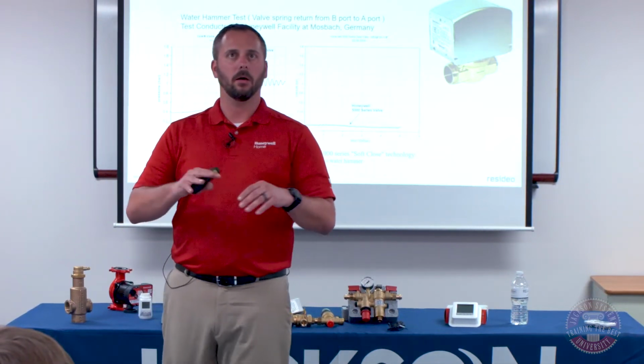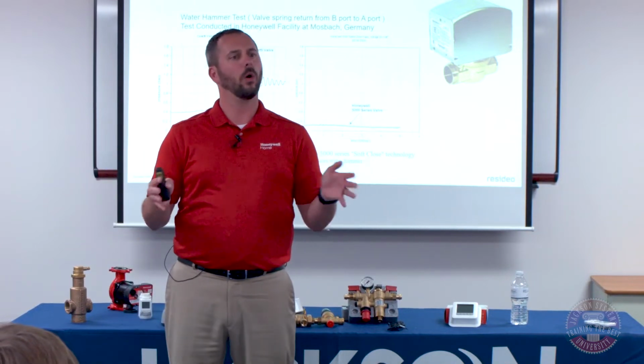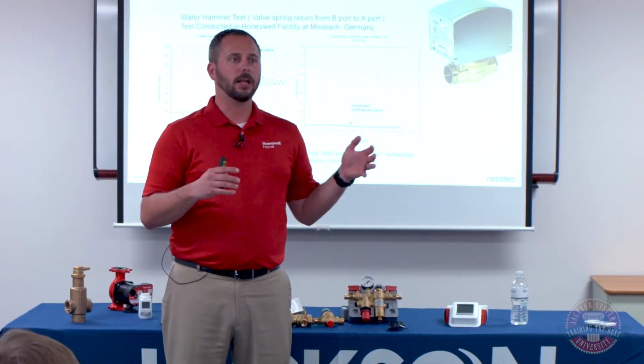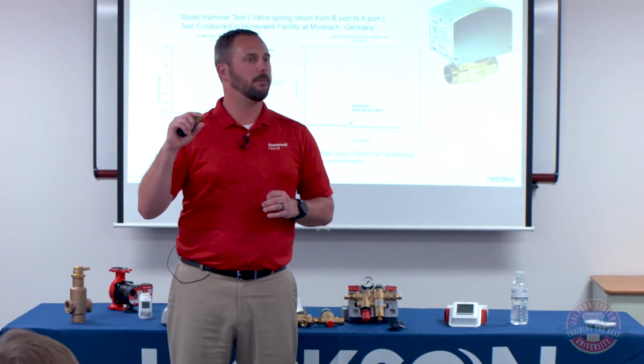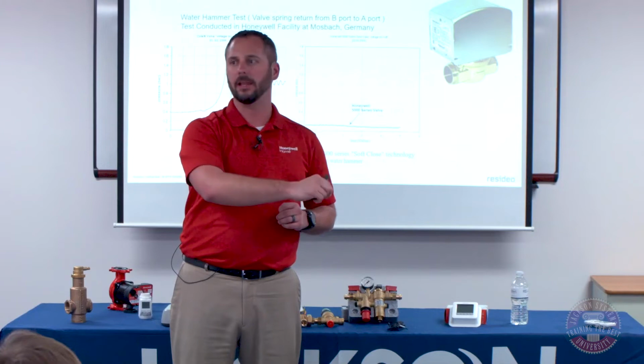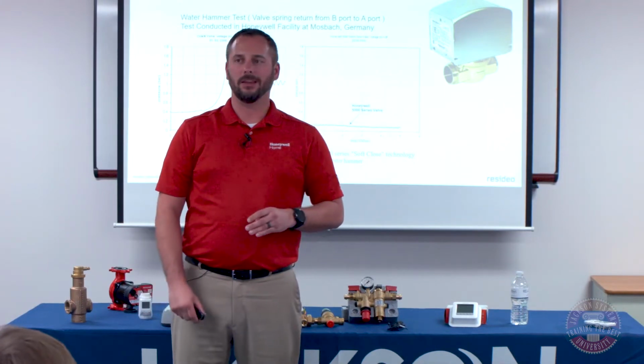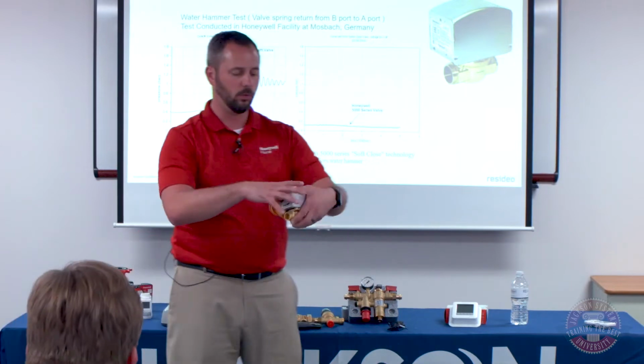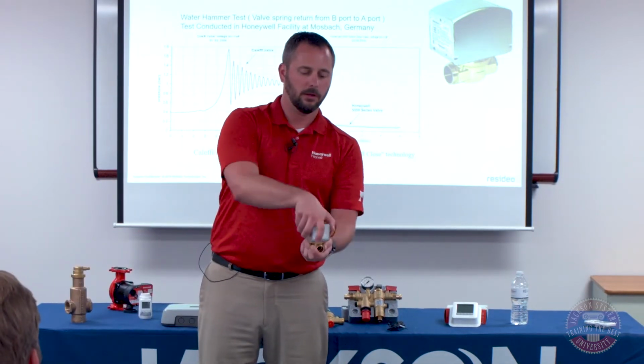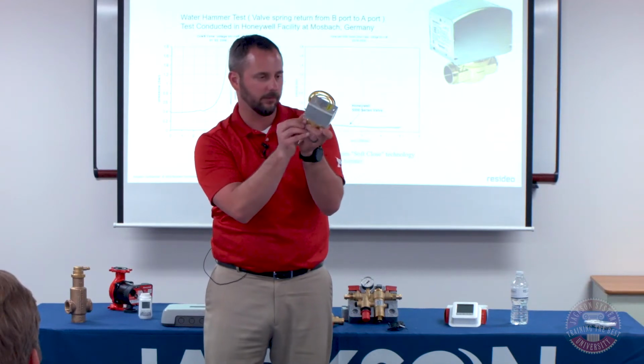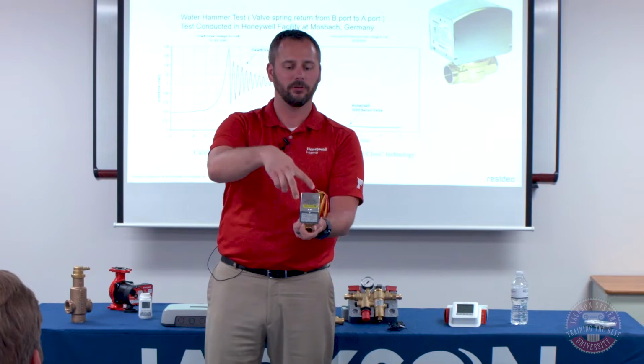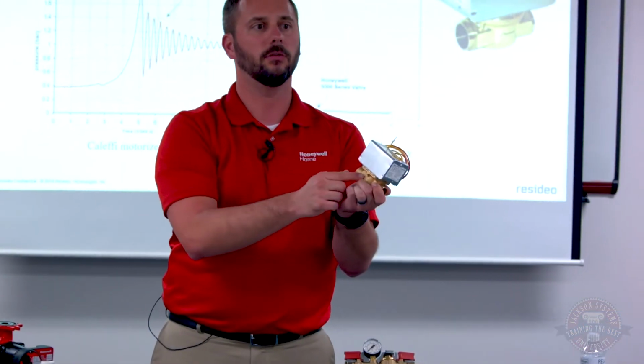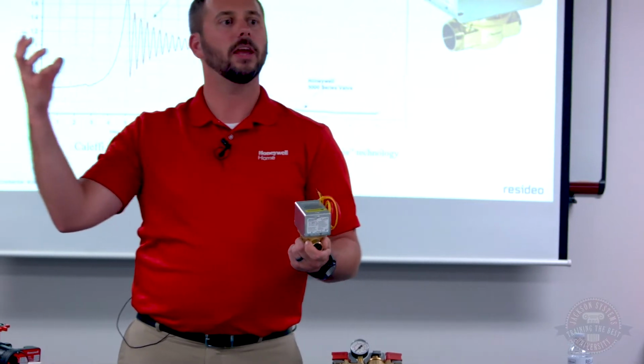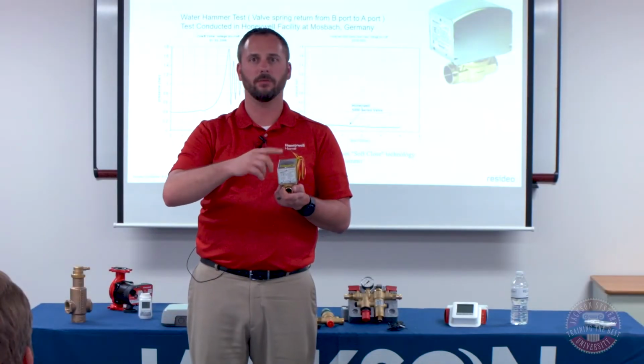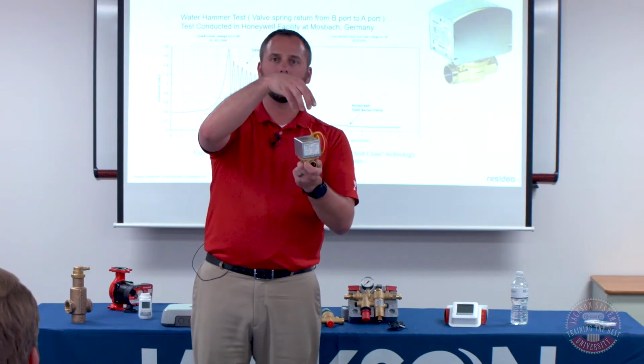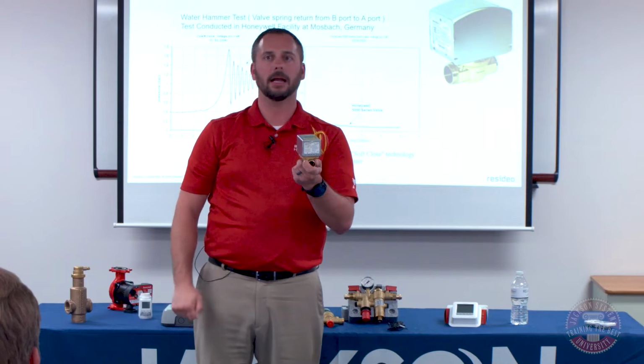I'm going to try to talk through this one a little slow. The 1000 series valve has the body and the power head on there. The 5000 is a slightly different body, but we have engineered it to retrofit onto the 1000 series bodies. It's as easy as, I don't have a screwdriver with me, but if you were to take this screw off, this comes off. There are 2 screws inside of here. Let's see if I can figure out which ones. They're caddy corner, so there are 2 screws securing the power head to the valve body. You remove those 2 screws, take the new 5000 series power head, and you can tell the difference because the 5000 has a rounded top. It plugs right back into the same spot, and 2 screws secure it back to the valve body.